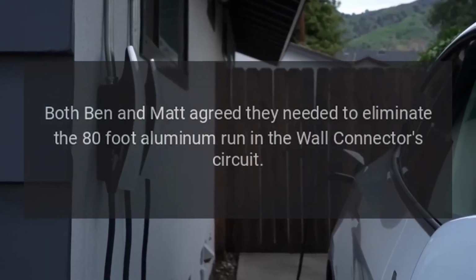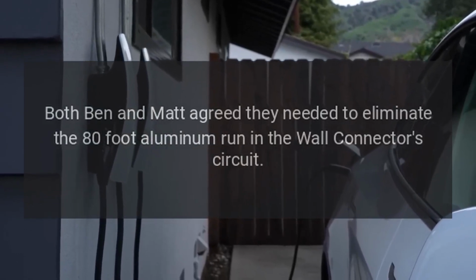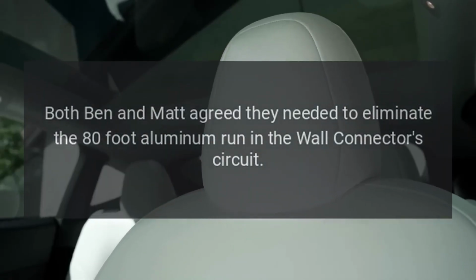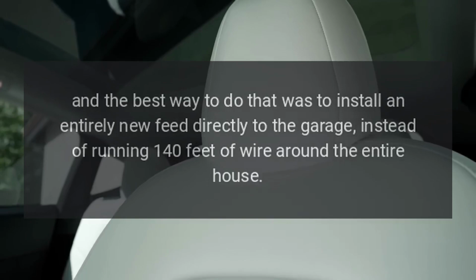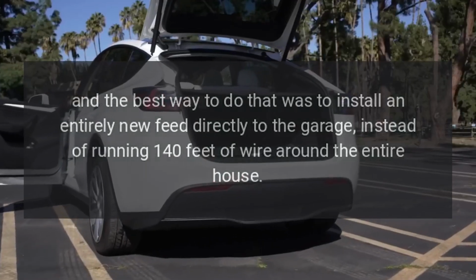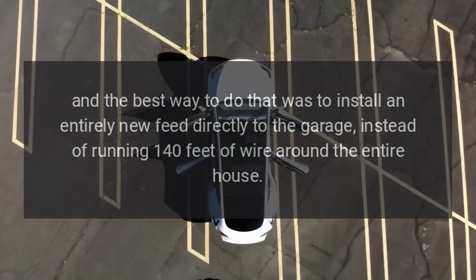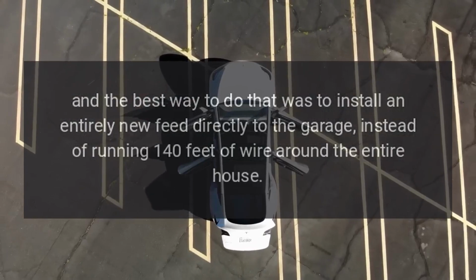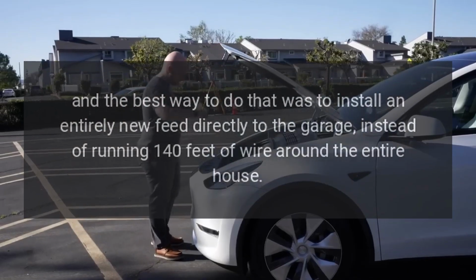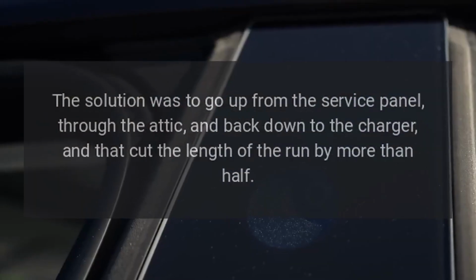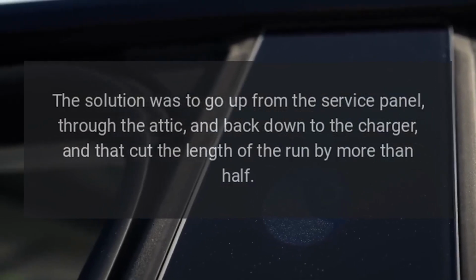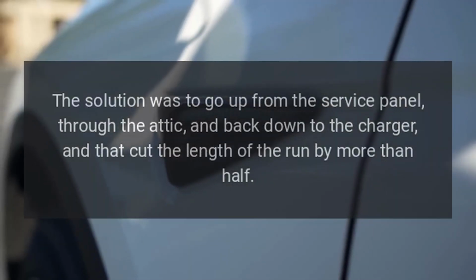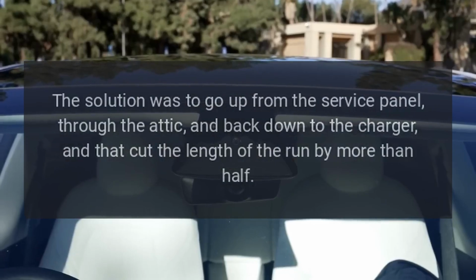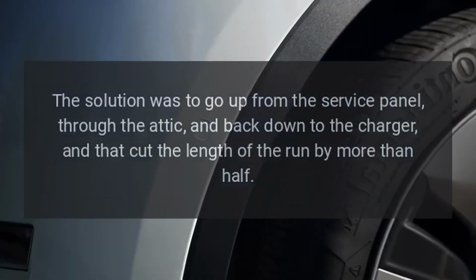Both Ben and Matt agreed they needed to eliminate the 80-foot aluminum run in the wall connector's circuit. And the best way to do that was to install an entirely new feed directly to the garage, instead of running 140 feet of wire around the entire house. The solution was to go up from the service panel, through the attic, and back down to the charger, and that cut the length of the run by more than half.